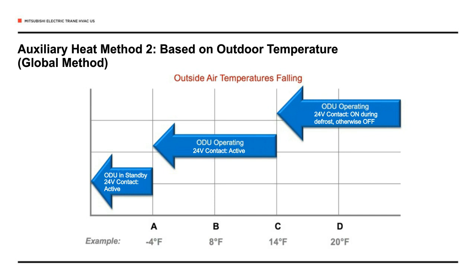So we can see here that in this case, our outdoor unit is running down to point C, which in this example is 14 degrees. Between 14 degrees and -4, we're running both the outdoor unit, the VRF condensing unit, and the auxiliary heat together. Once we get below point A, or 4 degrees below 0, we're only running our auxiliary heating system. So very important, if you're taking this approach, you want to make sure that, number one, you have all of your zones covered, since you're turning the VRF system off at a certain temperature. And also you want to make sure that the auxiliary heating system is sized for the entire heating load of the building. So two very important considerations.